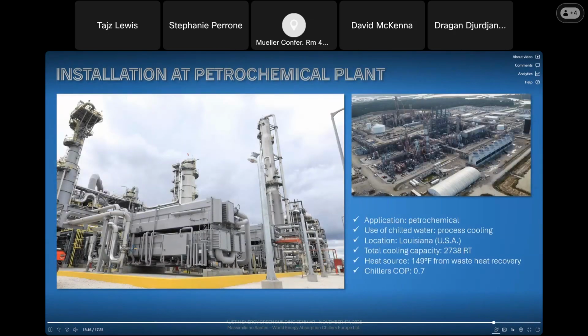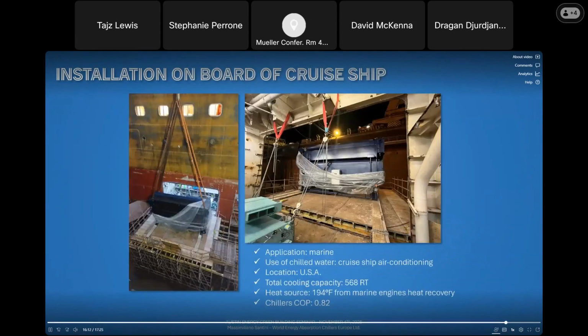Industries have a lot of waste heat. This is a petrochemical application in Louisiana in the USA, where we installed a total cooling capacity of over 2,700 tons using very low temperature, 149 degrees hot water from waste heat. Passenger ships have also waste heat. This case is 568 tons absorption chillers powered by 194 degrees hot water recovered from marine propulsion engines.